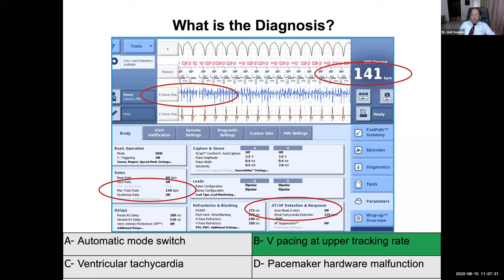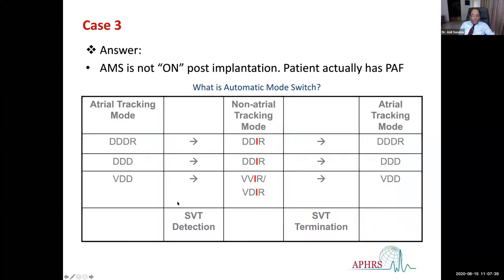Sorry about that. So the pacemaker is not changing to the mode because the mode switch is switched off. As Dr. Maha has already explained, when automatic mode switch is on, the pacemaker will change the mode to a non-tracking mode.